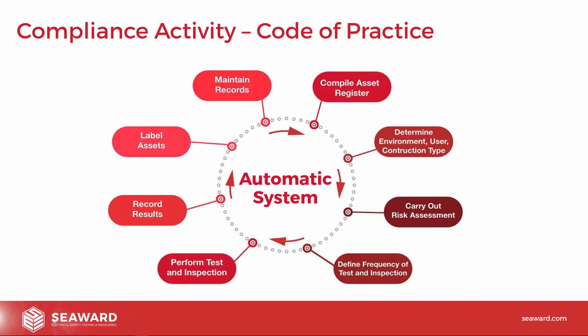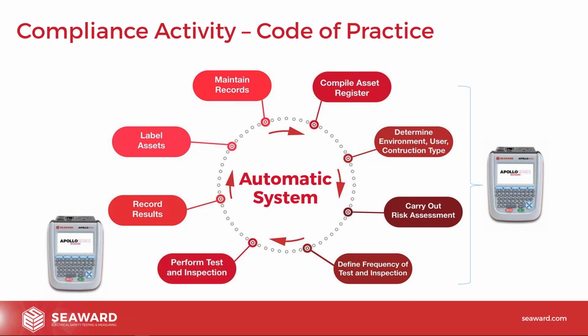So with an automatic system, we can actually use the tester. Now, something like our Apollo tester will compile the asset register. As you're typing each asset in, as you go through, it can automatically give it a number. You obviously type in the details for the asset. You can carry out the risk assessment on the tester, determine the frequency of test on the tester, and it stores all that as you go. So as you're testing the items, you're building up your asset register, you're doing your risk assessments, you're moving through, all automated quickly within the tester.